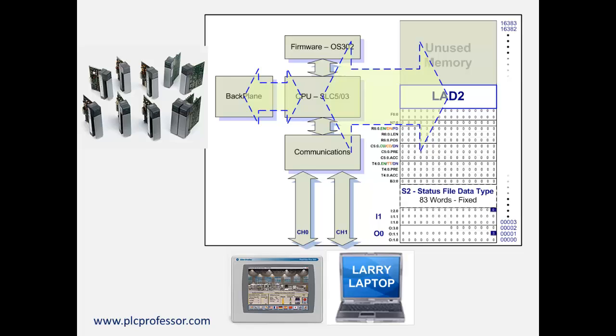The actual protocol for channel 0 is DF1. Channel 1, depending on the particular processor — here it shows a SLC 503 CPU — that's DH-485, data highway 485. If this were a 504, then channel 1 would be data highway plus. If this were a 505, channel 1 would be Ethernet.